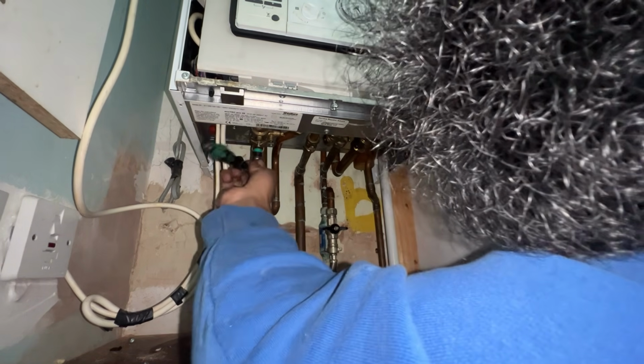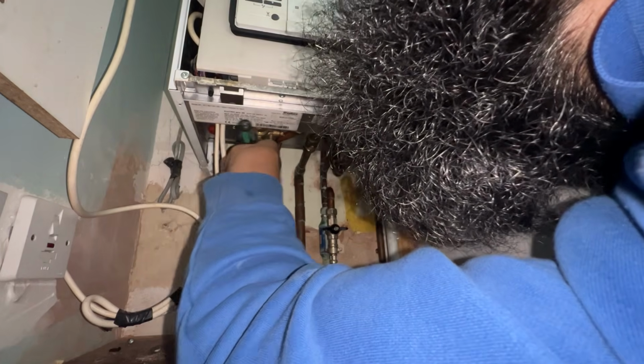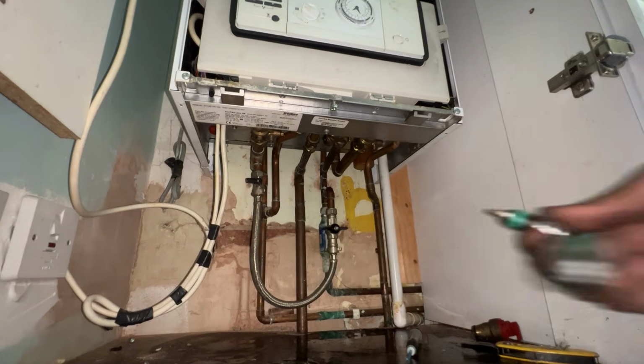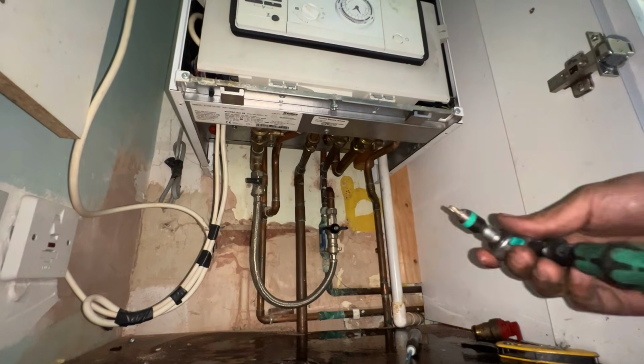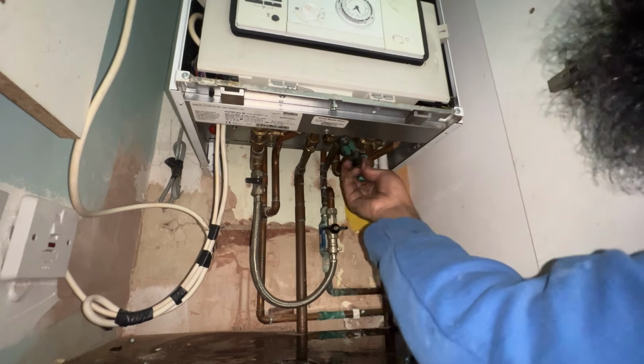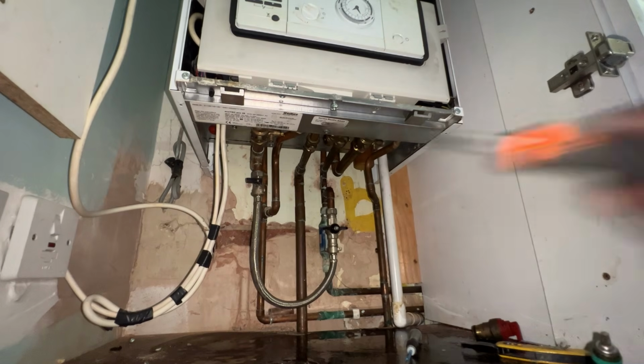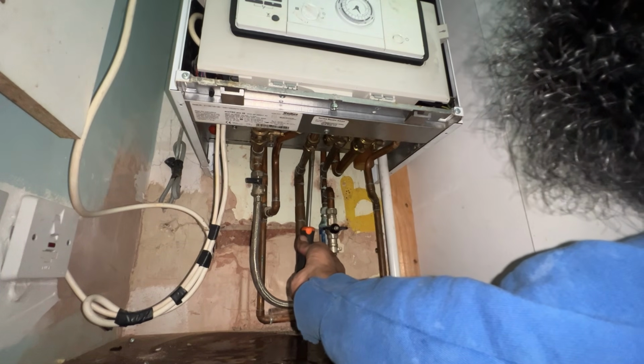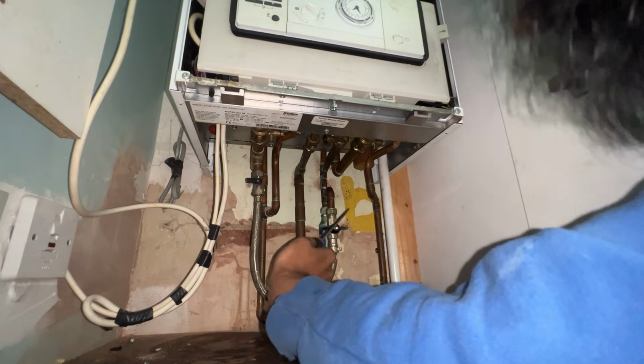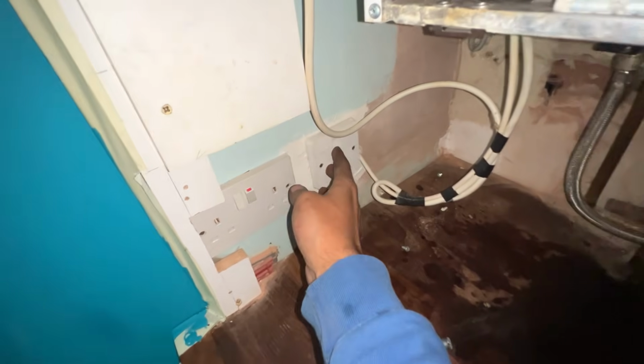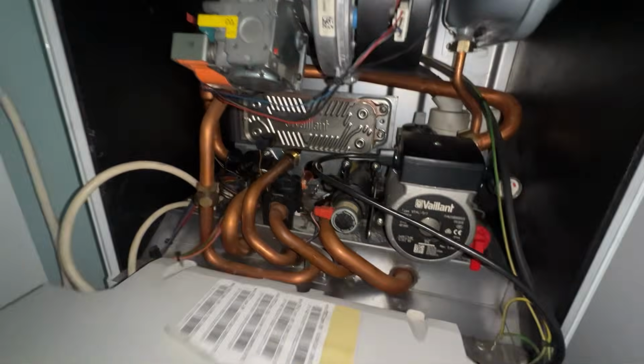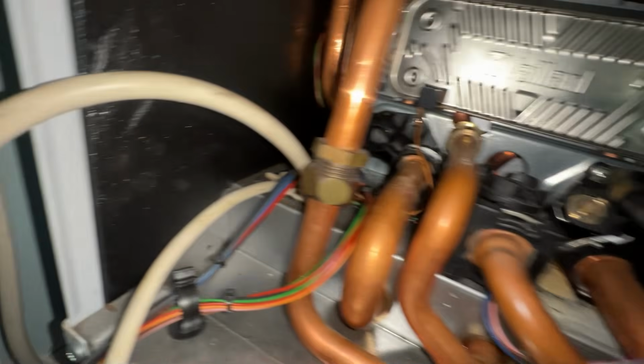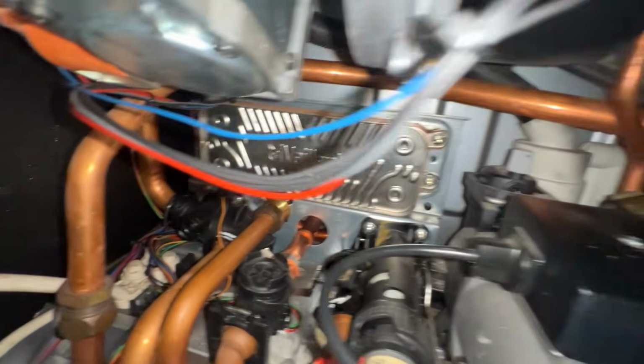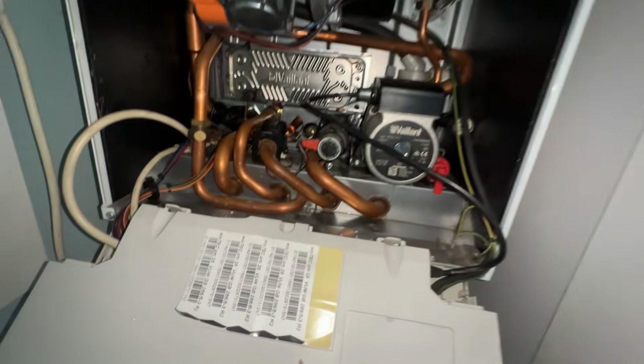Switch this over. Open up flow returns. You hear that? You hear that? All the air coming out. Great. Beautiful. Turn the gas back on. Turn boiler back on. Have a quick sneak inside, because if you've messed up now, you've messed up. If there's any leaks, you're done for. Doesn't look like it. I was concerned about that top one there, to be honest. No other concerns that I have.